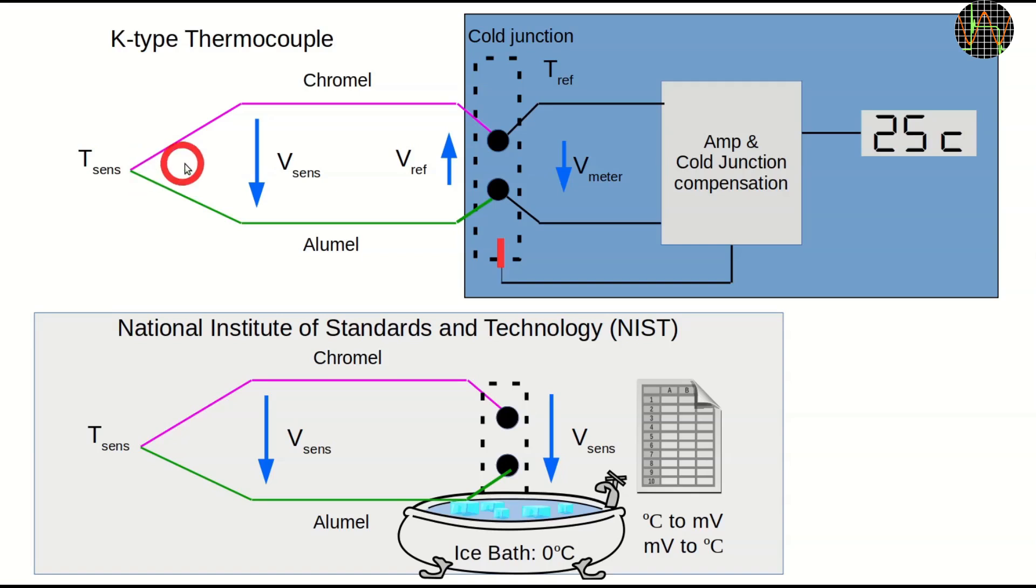The problem is that when you connect the other end of the thermocouple to your meter, you create inevitably another set of metal to metal junction which produces their own tiny voltage depending on their temperature. The standard millivolt to degrees temperature conversion as maintained by NIST assumes that this second junction is kept at 0 degrees Celsius, like an ice bath. Hence it is called cold junction.